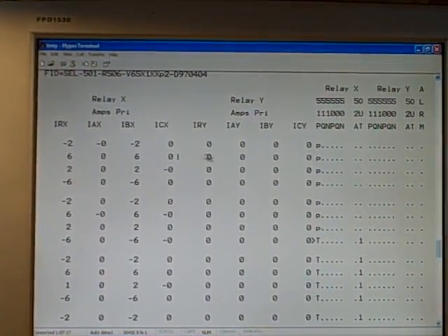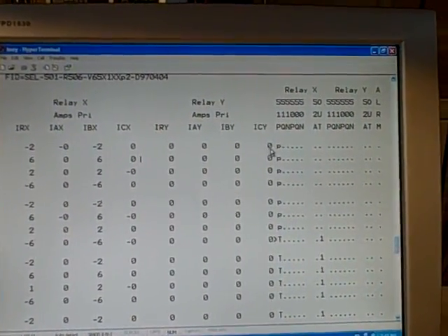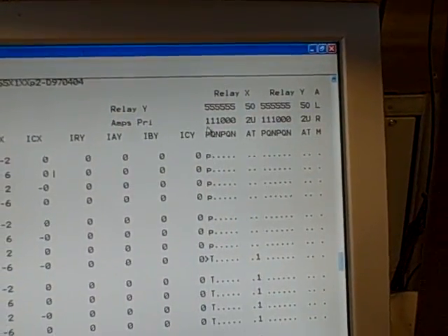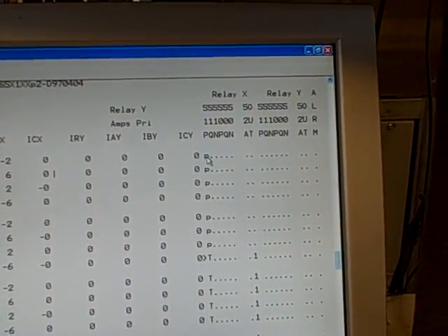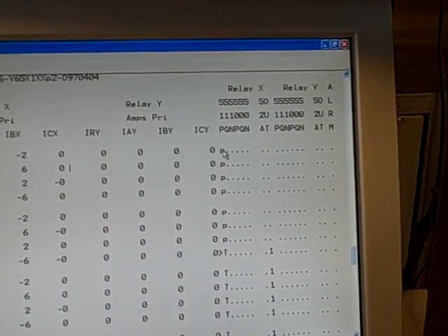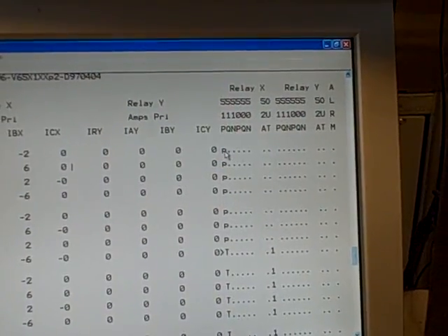Notice that we show over here the letter P under the 51P column, lowercase letter p. And that tells us it has picked up.